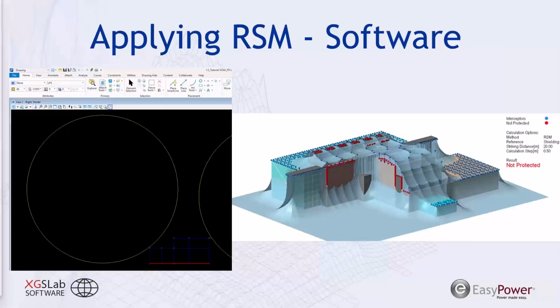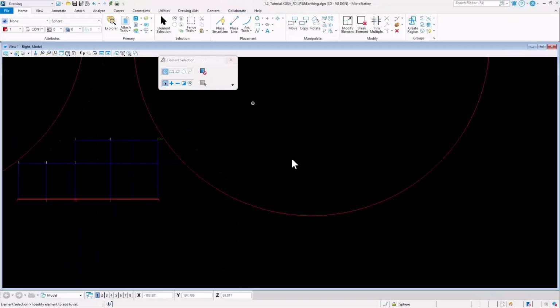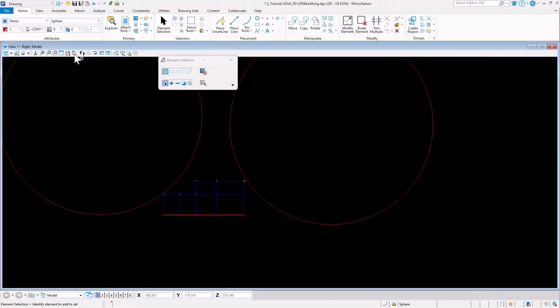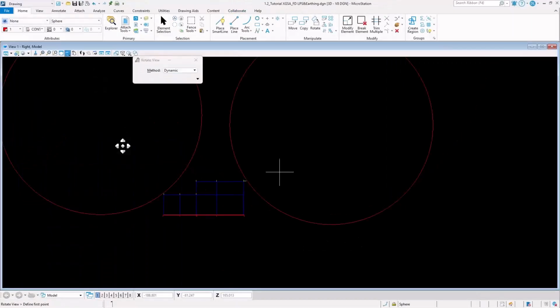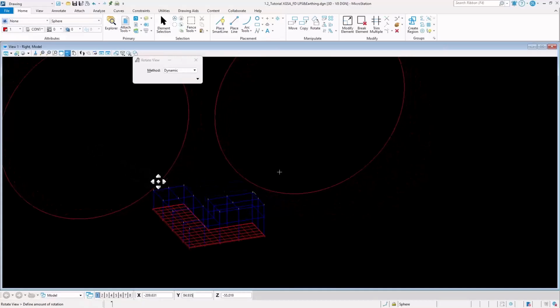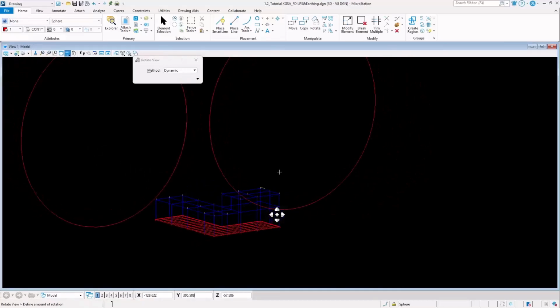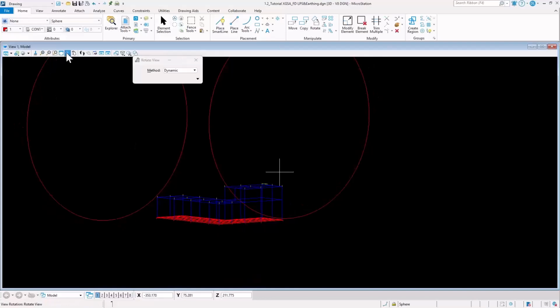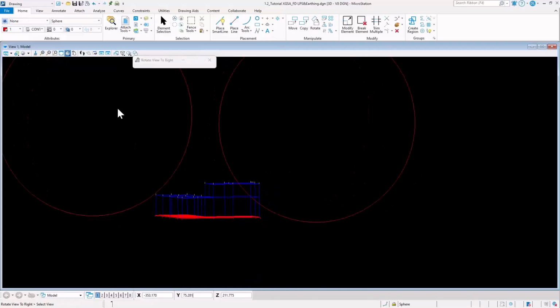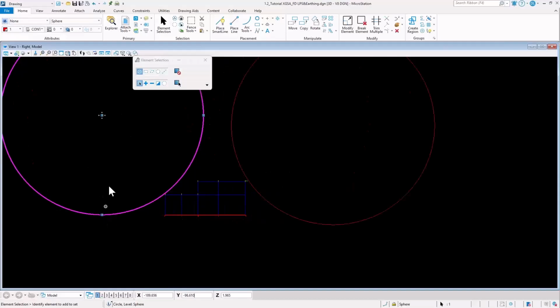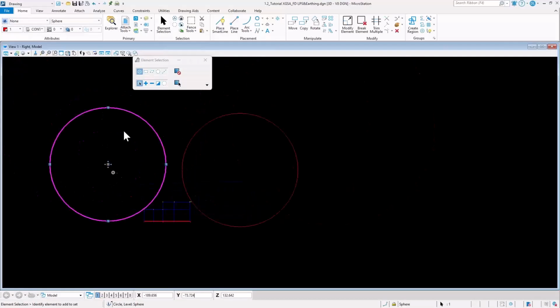One of the simplest ways, if we have, let's say, MicroStation, for instance, I already have a very simple illustration here. So I will rotate my view. You can see this is just a wireframe of a simple building. And if I rotate from the right, I have a sphere size. And this one is 150 feet across, or 150 feet as the radius. So it's the 45 meter radius NFPA value.